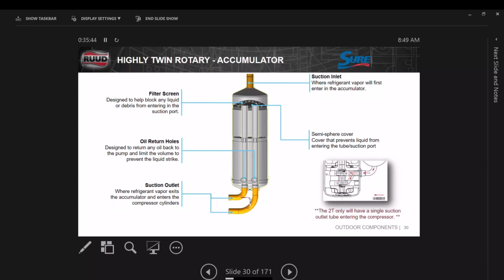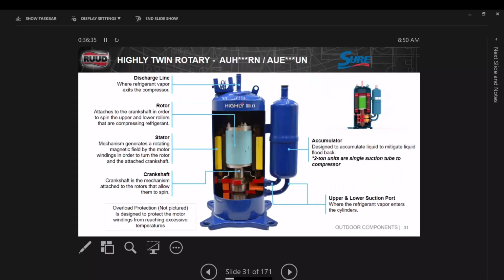At the bottom, you see some oil return holes. This is to pull the oil out of that accumulator at the bottom to get it back into the system. You notice it has two suction lines coming out the bottom going into the compressor. The 2-ton is only going to have one, but we need the volume of refrigerant coming out for anything bigger than a 2-ton going into the twin rotary compressor.